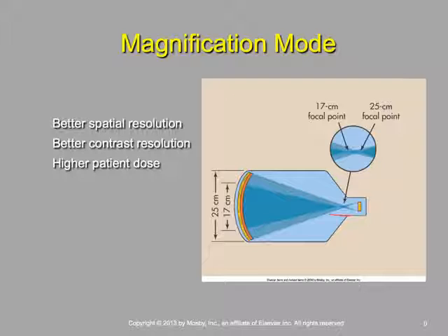Talked about with conventional fluoro, one of the main differences between conventional and digital is the amount of mA that's being delivered to the patient. With conventional fluoro, we're probably talking about an MA of like 5. An MA of like 5 in conventional, right? 5 MA.